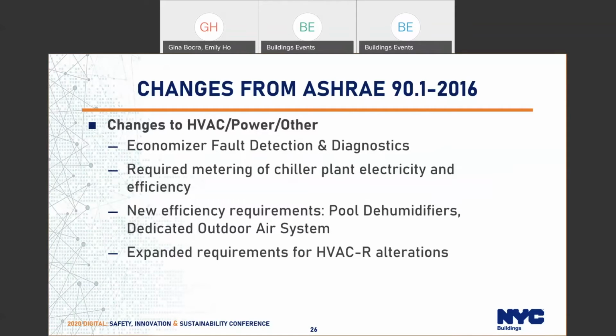For HVAC, power, and other, one of the changes is now a requirement that if an economizer is provided, it also has to be equipped with fault detection and diagnostics. This was a requirement in the ECC for a few years, and ASHRAE adopted this language into this compliance path. So you can see ECC and ASHRAE are becoming a lot more in alignment. They're taking code sections from each other that weren't present before. If you're designing a chiller plant and following ASHRAE 90.1, there are a lot more stringent metering requirements. There has to be real-time metering of the electricity consumption and the efficiency rating of the chiller plant, pretty much in real time. So that's a new requirement and very important if you have a large chiller plant.